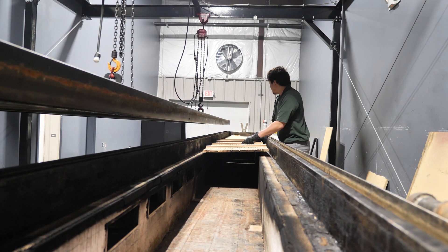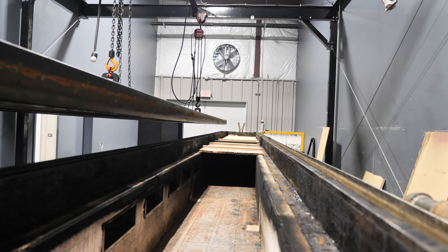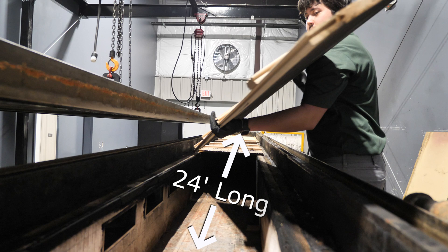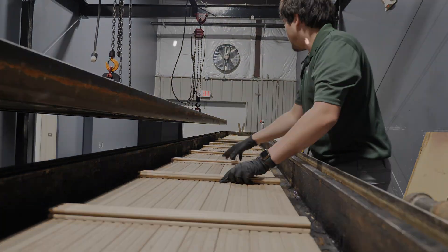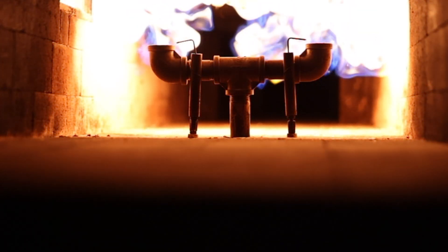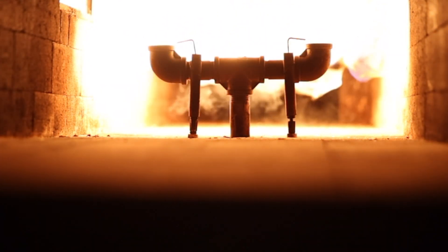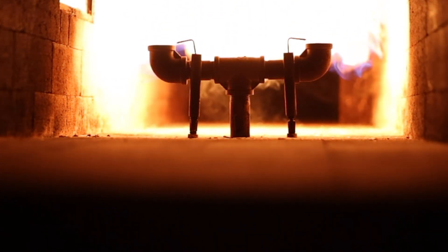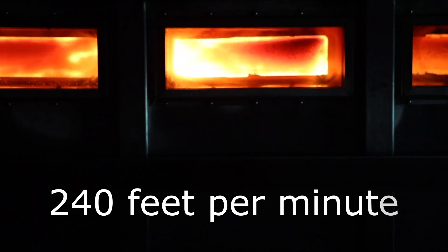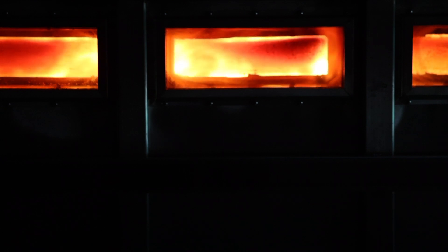These standards are used to regulate and select materials for interior building construction throughout North America. The test involves assembling a specimen and mounting it into the roof of a non-combustible horizontal box or tunnel. The test specimen is 24 feet long and approximately 2 feet wide. The tunnel is 12 inches high, and the apparatus has two gas burners providing a flame and a blower to move air and combustion products at a controlled velocity of approximately 240 feet per minute.